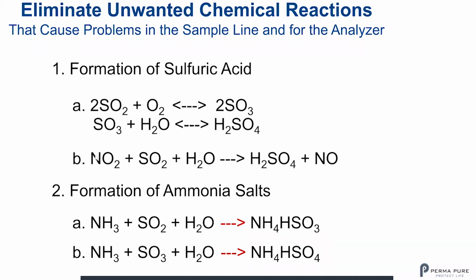We also have the potential to do it in this way too. NO2 plus SO2 plus H2O gives you sulfuric acid plus NO. This also changes your readings as well. So this formation of sulfuric acid is reduced if we can eliminate that water coming out of the cooler, the water vapor coming out of the cooler.